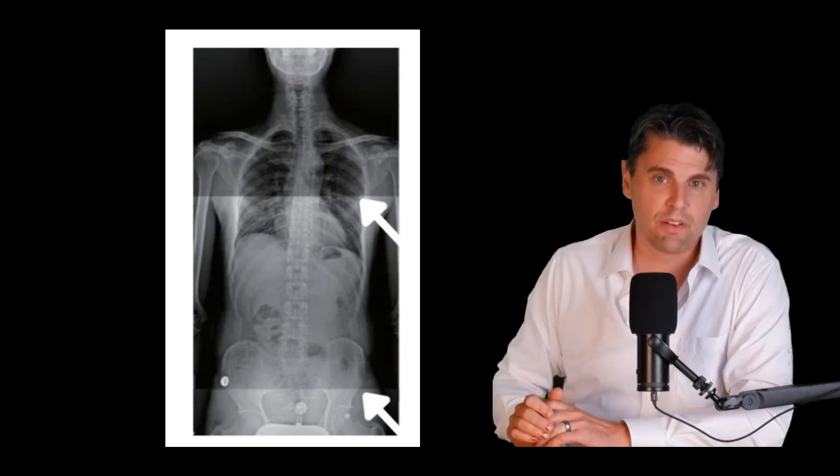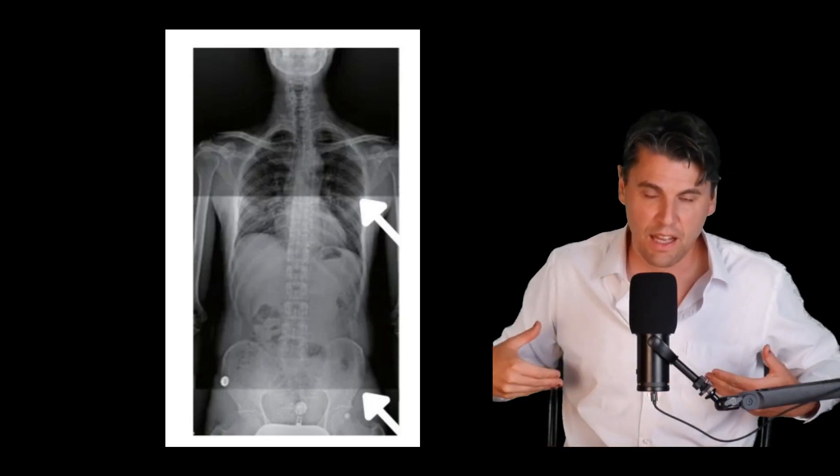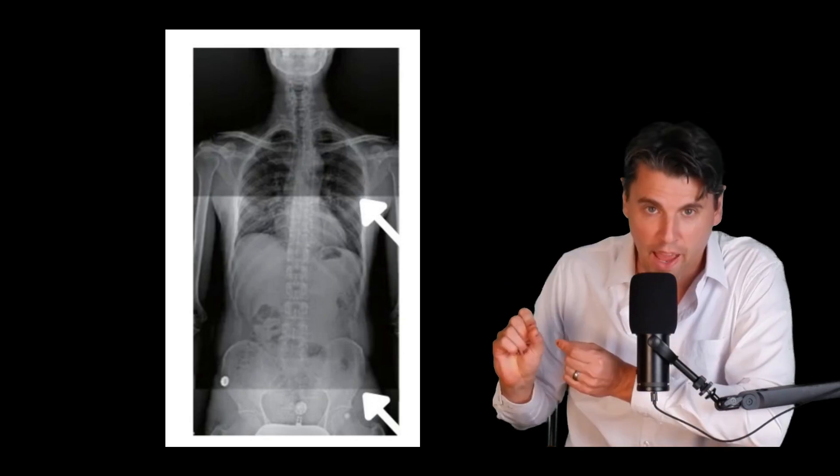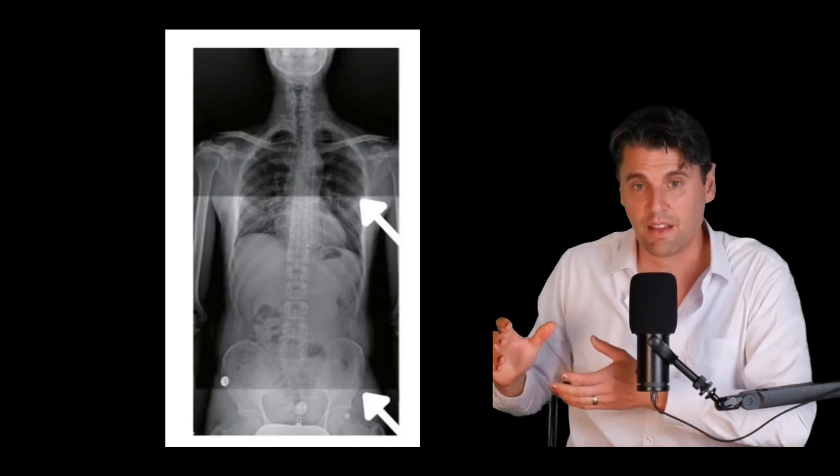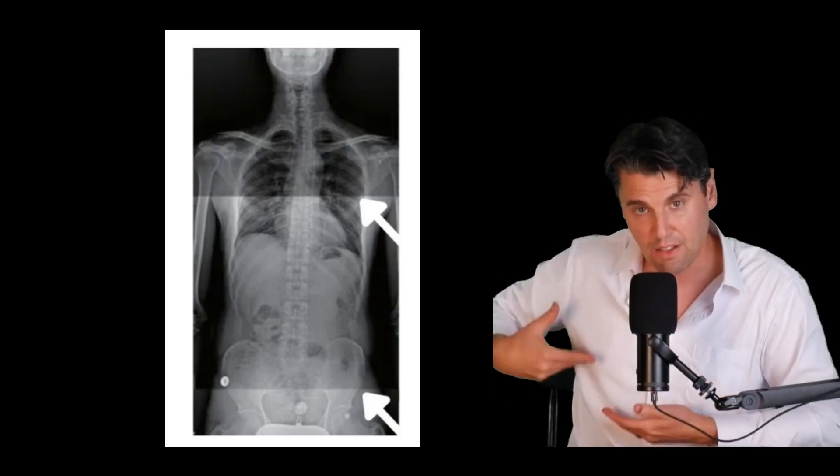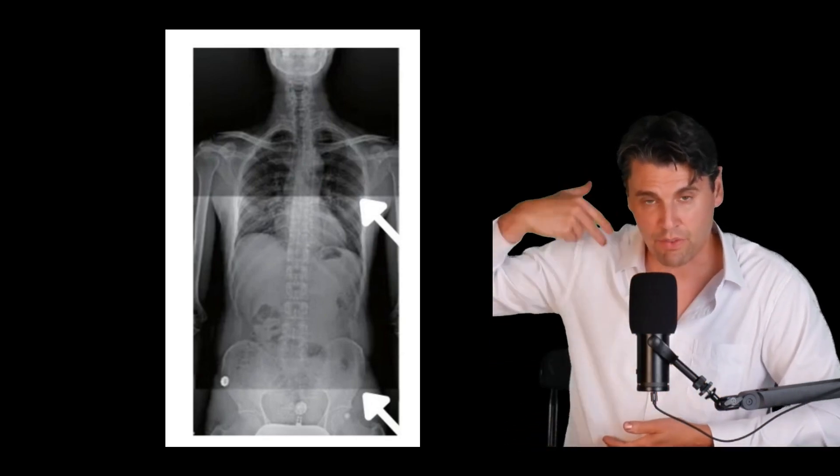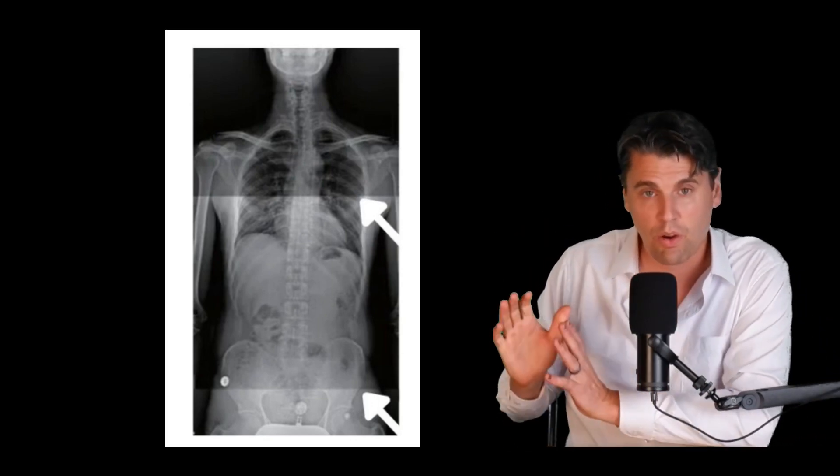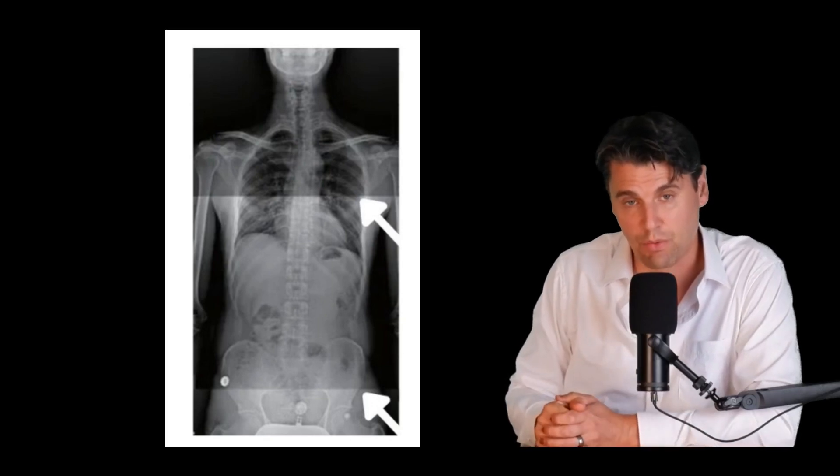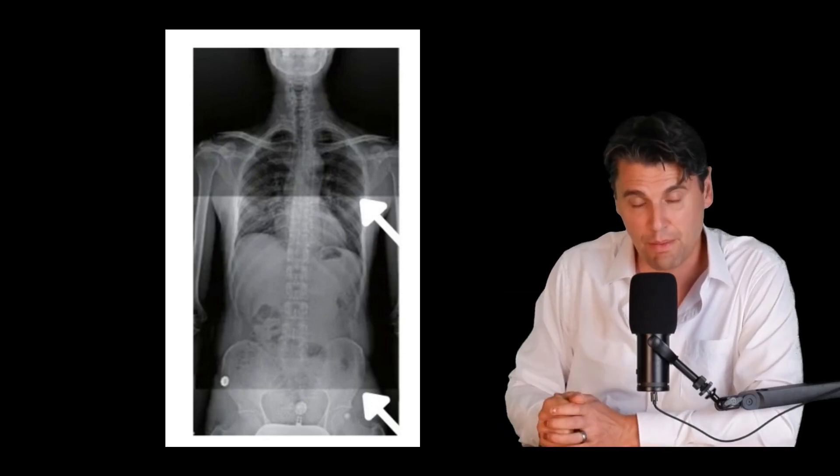But sometimes there's kind of imperfect stitching due to actual physical effects such as the change in the intensity across the superior inferior direction of the beam, or the change in the actual energy of the beam.